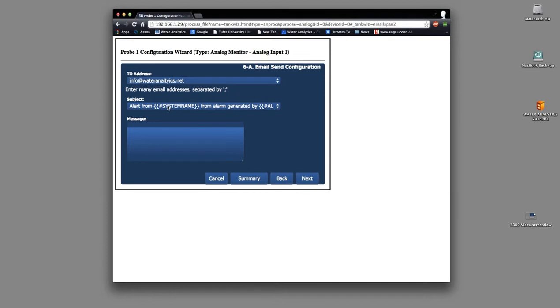For the subject and the message, I can insert variables, like you see here, system names, that report details on the process like the 2300 name or the alarm trip point. In fact, there are 11 settings and values that you can insert into your email message and your subject. I can even enter multiple email addresses so that several people can receive the message. This is a low pH alert, so my message will say your pH is below 6. Better do something fast. Okay. All right. Everything looks good, so I'll hit submit.